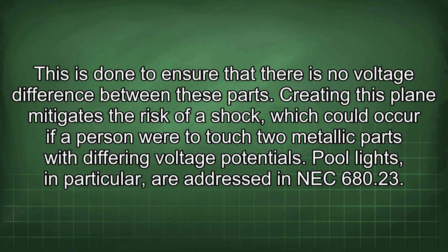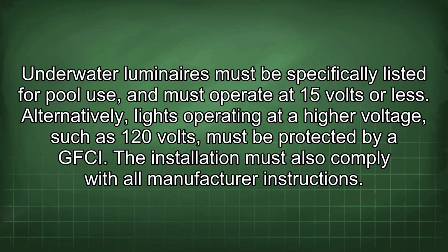Pool lights, in particular, are addressed in NEC 680.23. Underwater luminaires must be specifically listed for pool use and must operate at 15 volts or less. Alternatively, lights operating at a higher voltage, such as 120 volts, must be protected by a GFCI. The installation must also comply with all manufacturer instructions.